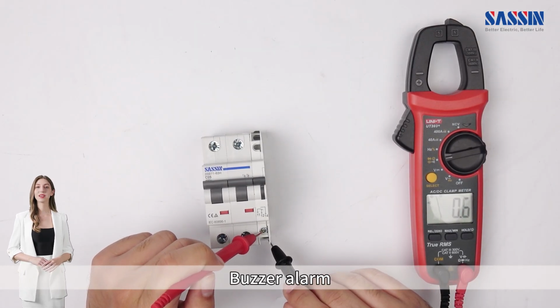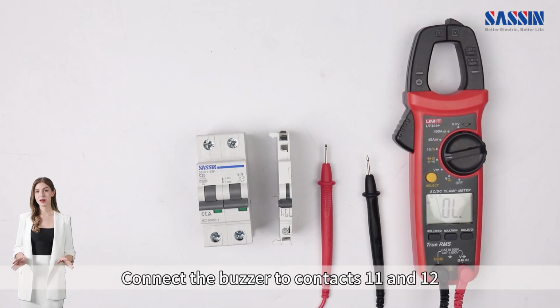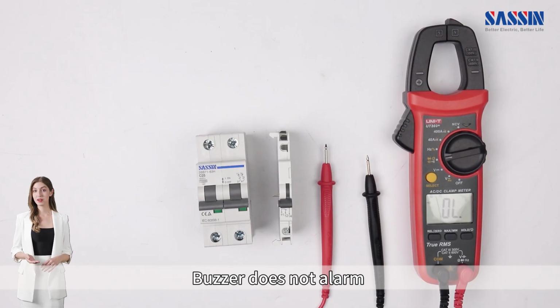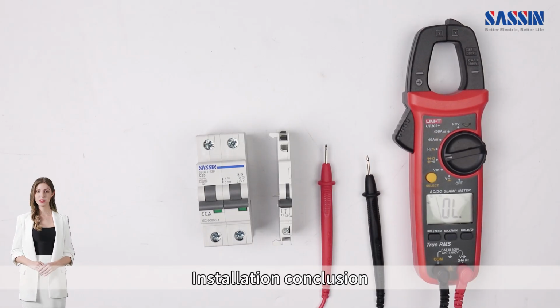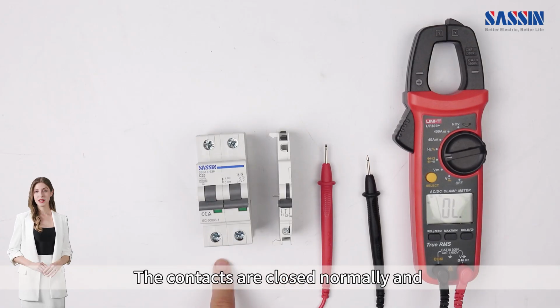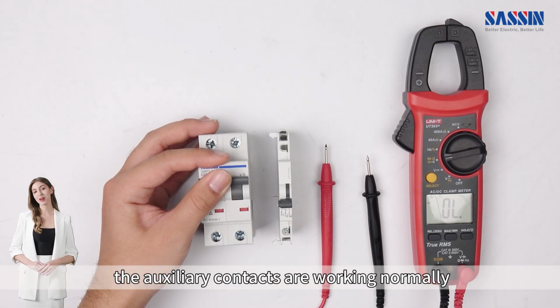Buzzer alarm. Connect the buzzer to contacts 11 and 12. Buzzer does not alarm. Installation conclusion. The contacts are closed normally and the auxiliary contacts are working normally.